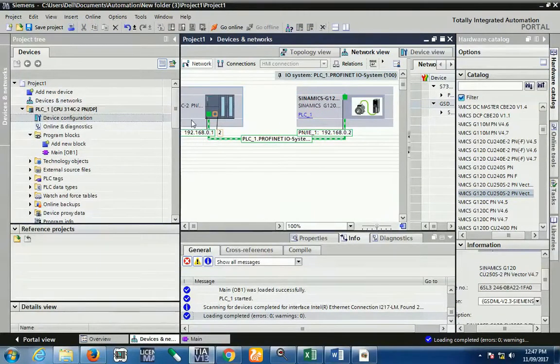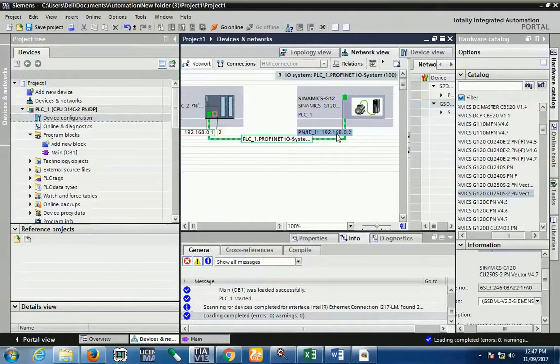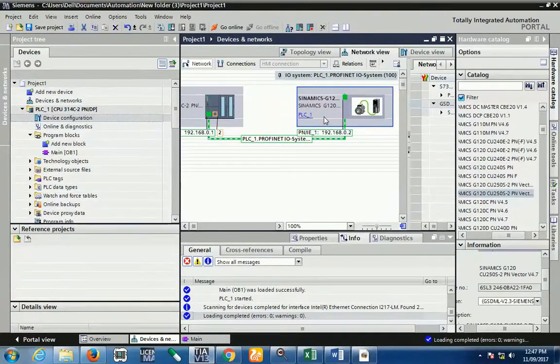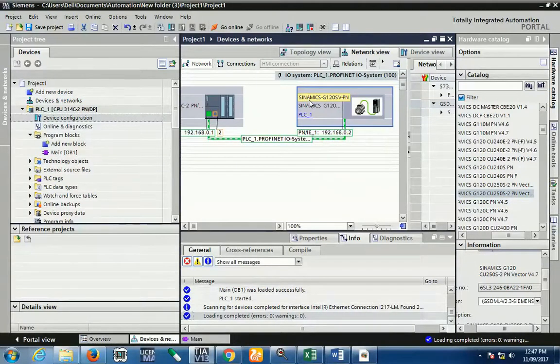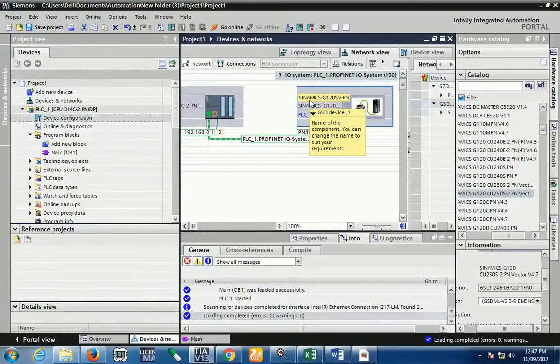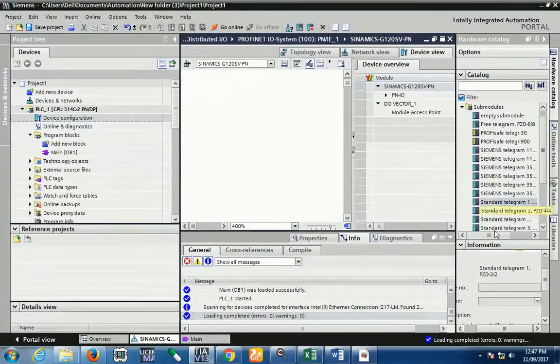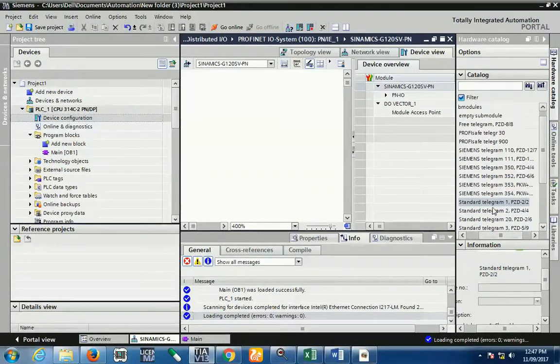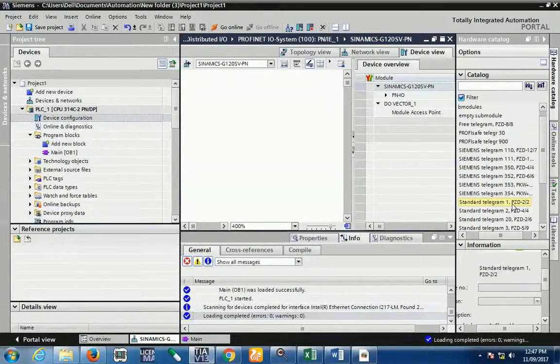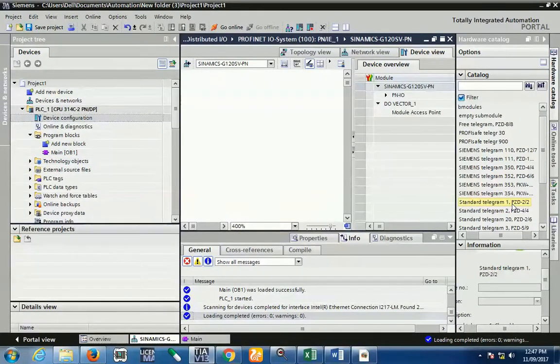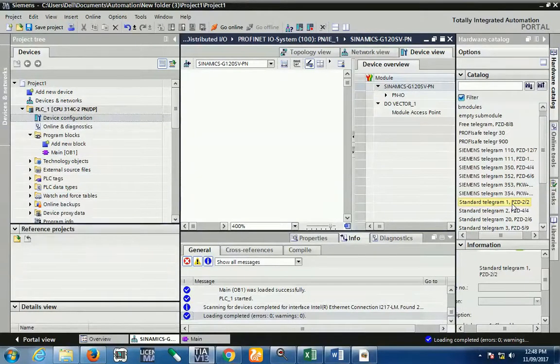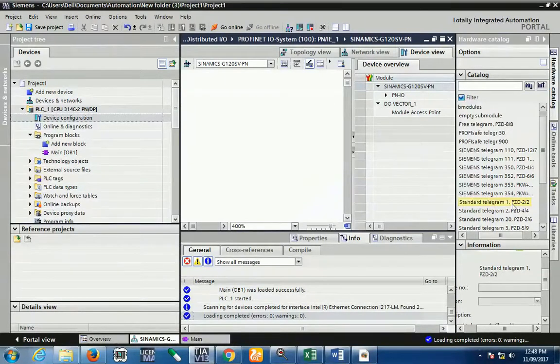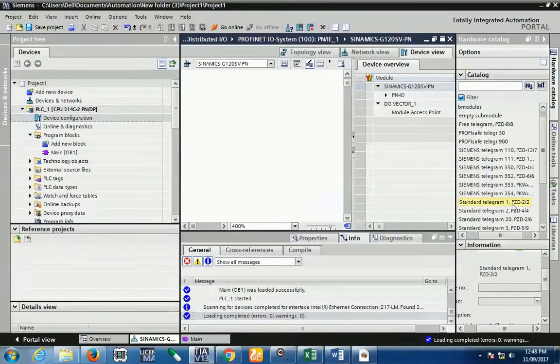And the SIEMENS AG and the series is Sinamics. And here we have used G120 CU250S, version is the 4.7. So this is right now my part number. So I just drag and drop here and assign the Profinet network. You just see the IP of my PLC is 192.168.0.1 and the IP of my drive is 192.168.0.2. So here we have used the standard telegram 2x2. Means 2x2 means we have used 2 data from read side and 2 data from write side. So in this case we have used for writing some data. So your first word is always control word and the second word is always reference word.